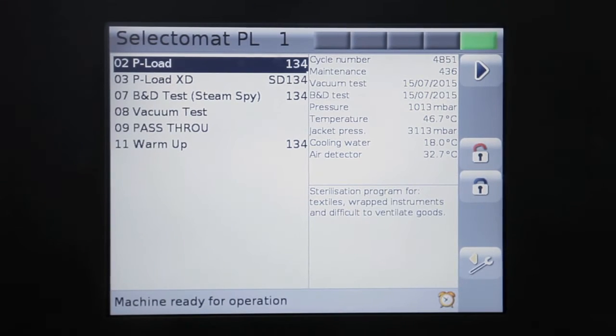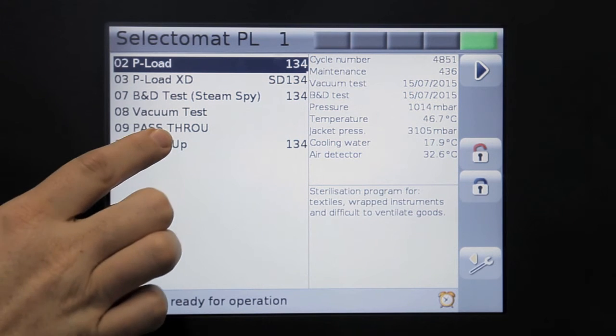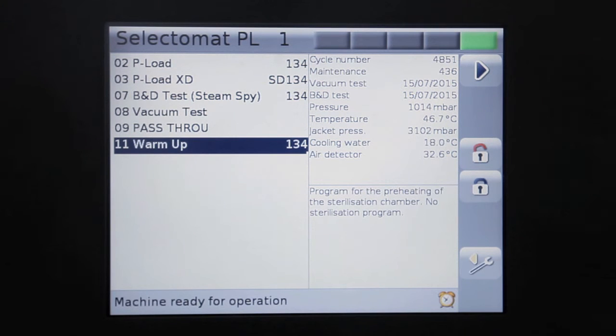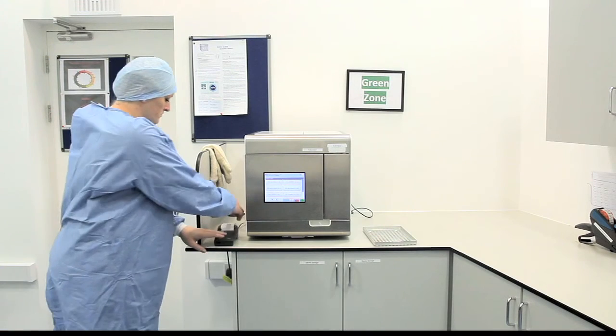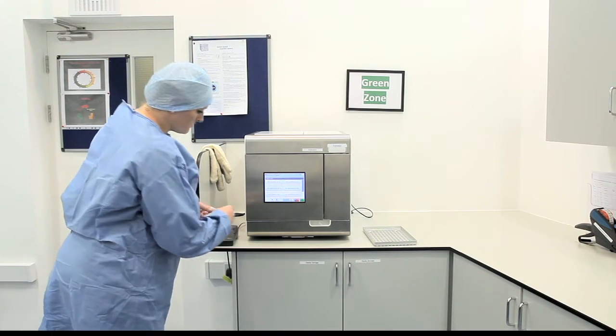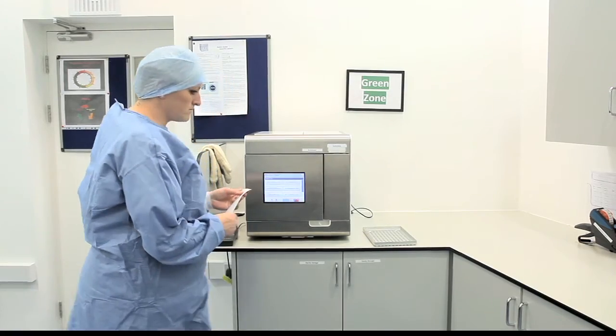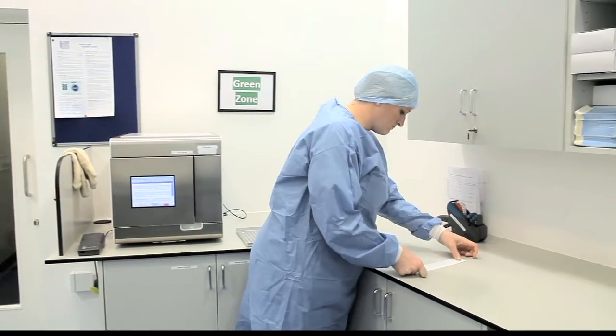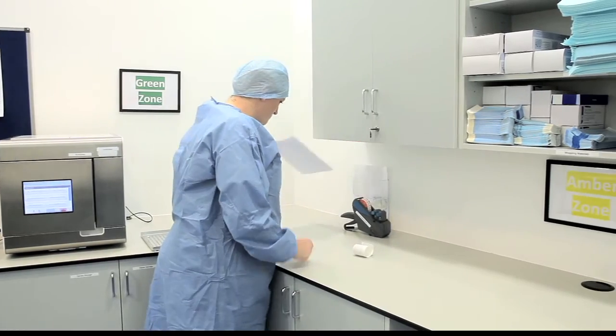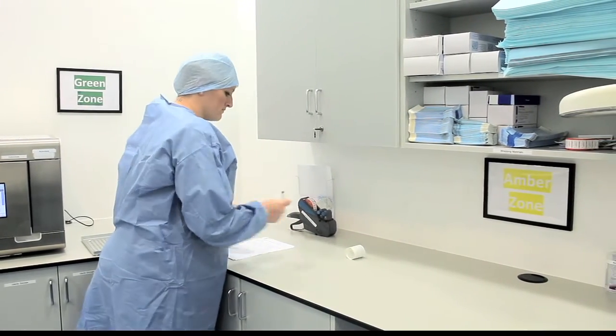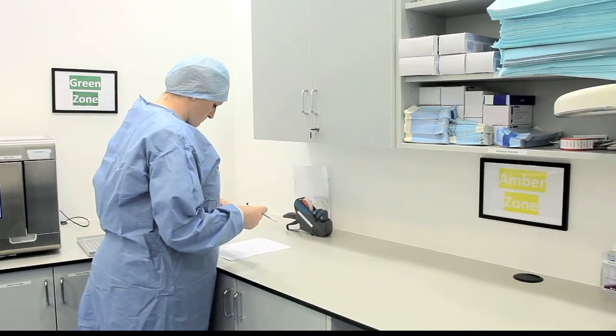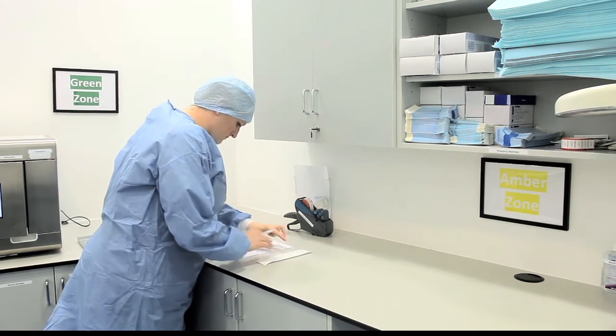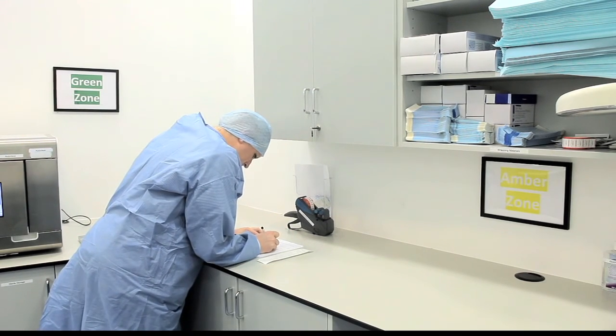The warm-up cycle of the autoclave is required to be carried out first thing each morning. The warm-up cycle is used to raise the temperature of the autoclave before the tests are carried out. This cycle may be selected from the types of cycles listed on the autoclave. If the autoclave does not offer a warm-up cycle, a warm-up can still be performed by selecting a Bowie and Dick cycle on the autoclave without placing a Bowie and Dick test into the autoclave. If a warm-up cycle is not completed, all subsequent tests will fail.